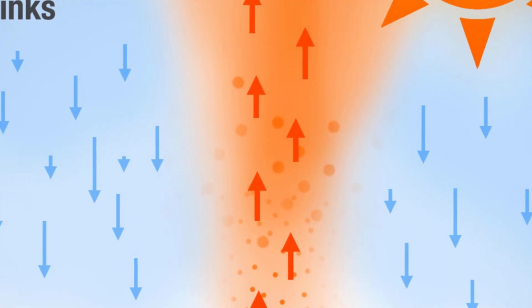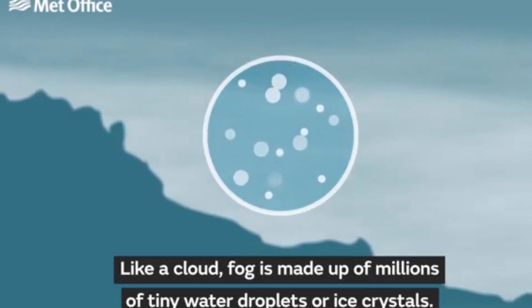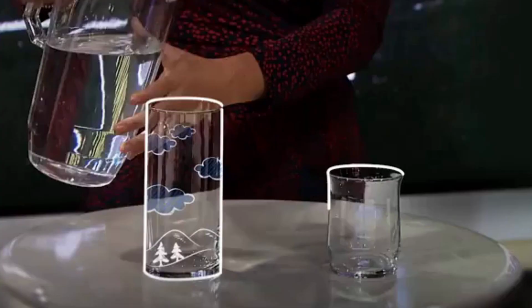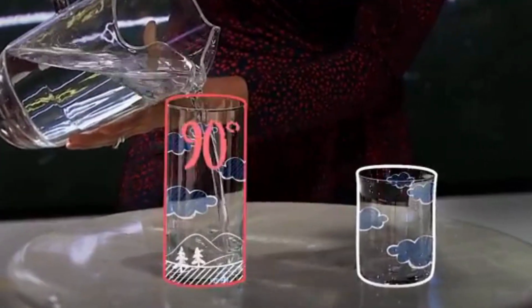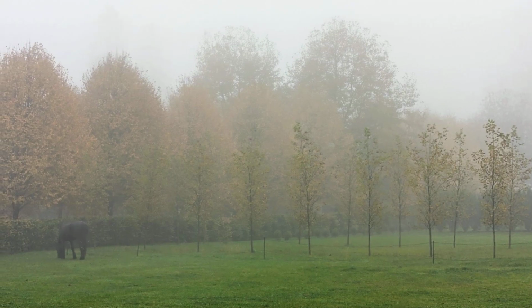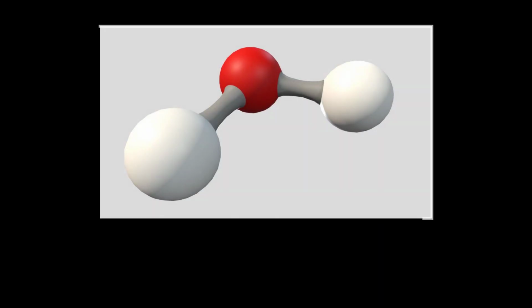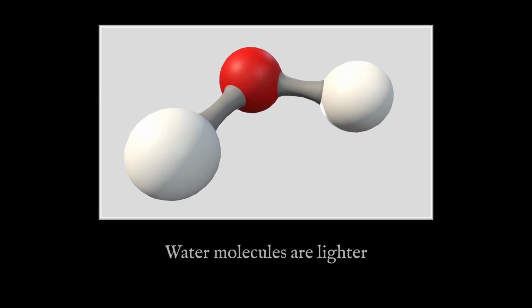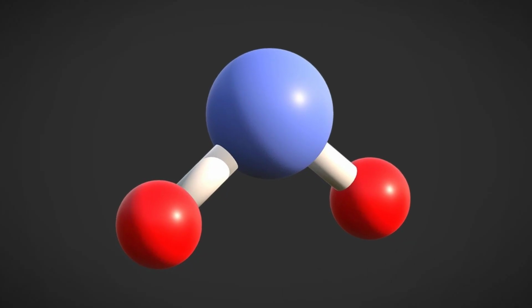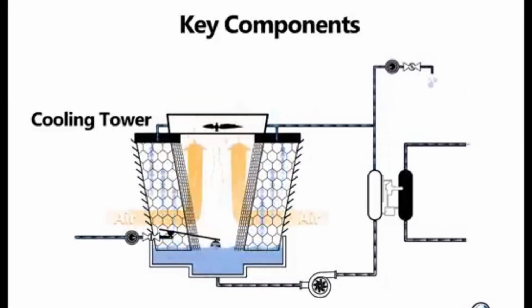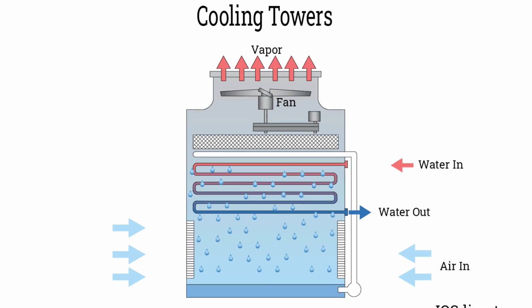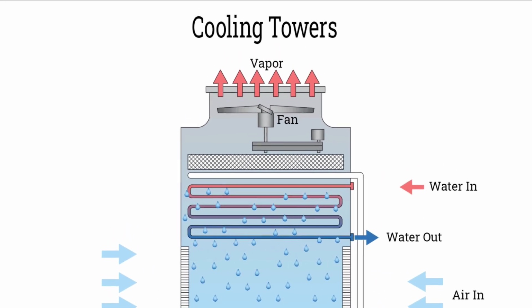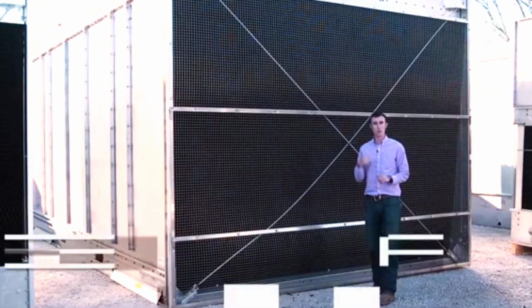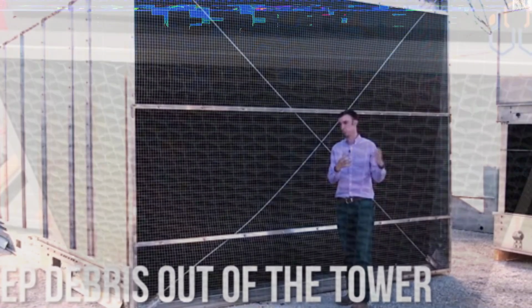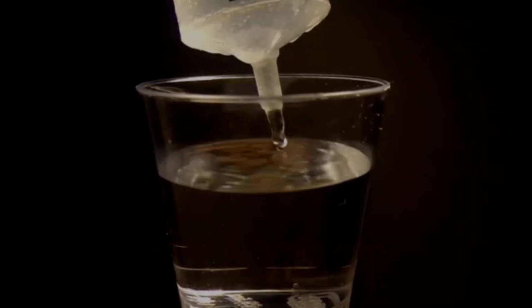We all know hot air rises. Less intuitively, the same principle applies to humidity. Holding temperature constant, increasing the water content in the air actually decreases its density. This is because water molecules are lighter than the nitrogen or oxygen molecules that make up most of our atmosphere. Consequently, humid air is more buoyant than dry air, a phenomenon that forms the second key principle of a cooling tower, convection. As the hot water transfers its heat to the air, the air warms and becomes buoyant, rising within the tower and drawing in fresh air through the bottom intakes.